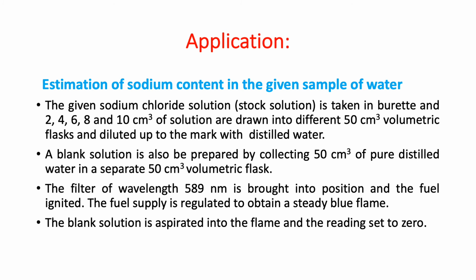Now you have to switch on the flame photometer. Take the blank solution, meaning the solution where you have not added sodium chloride solution, which contains only distilled water. Aspirate it into the flame and adjust the flame photometer to 0, meaning it doesn't contain any sodium ions. Why do this?